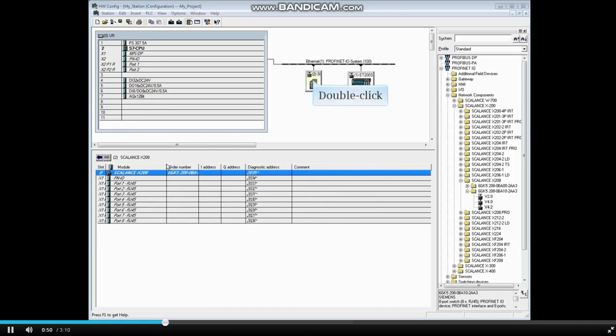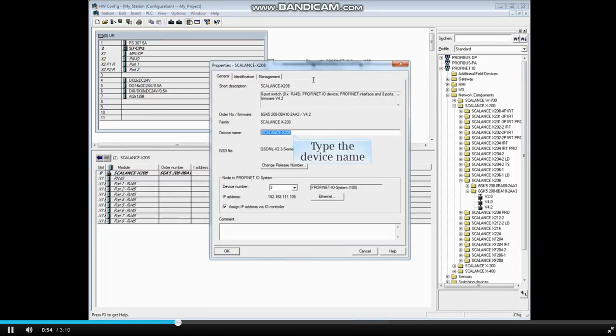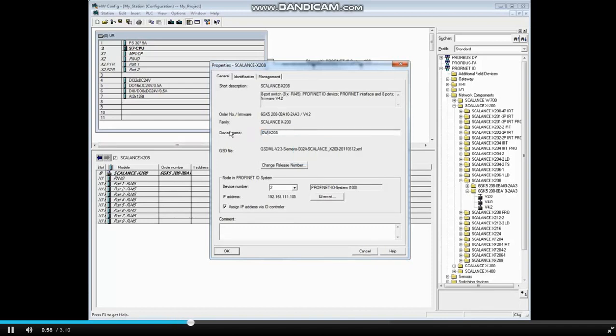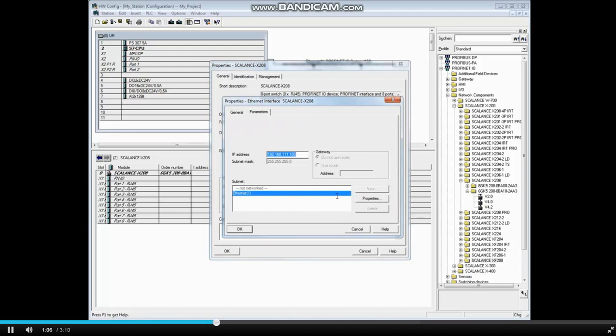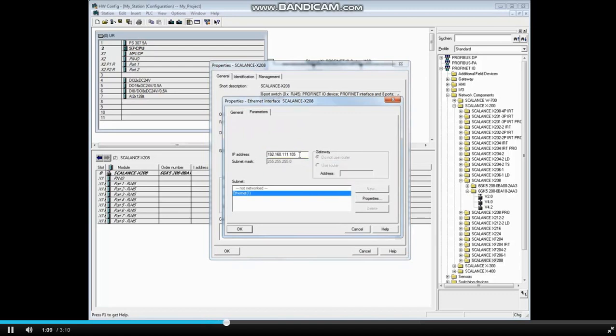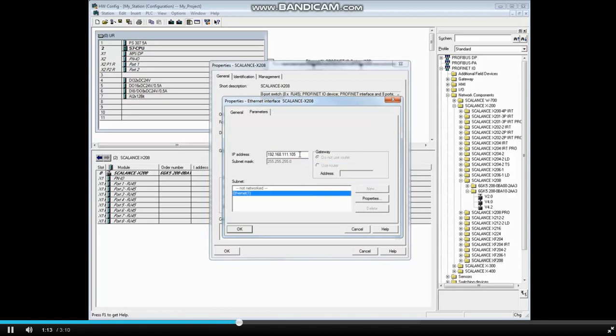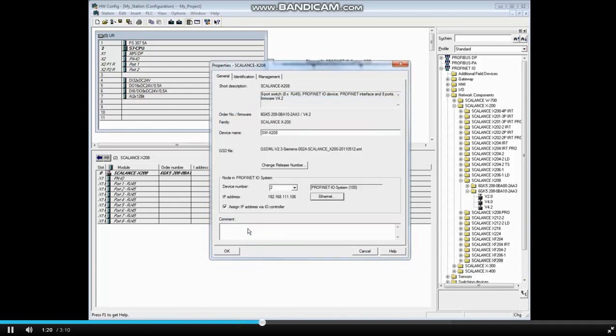Double click the switch to open its properties. Let's rename the switch. We'll call it SW-X208. Now click the Ethernet button. Now set the IP address. We'll make the switch 192.168.111.105 to be unique on the network. Click OK and OK the properties window.